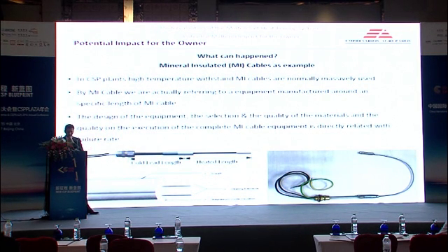I think I'm extending too much, so let me add: many people think that because heat tracing is made with cables, it's just a matter of off-the-shelf material. This is typical, though not the only way to do it, and not applicable to every circuit, but the most used are mineral insulated cables. They don't look much like a cable, more like an antenna or a thermocouple. It's equipment, not just a cable, it has two weldings, it works at 100 to 200 Celsius, expands and contracts, and is very sensitive to quality.